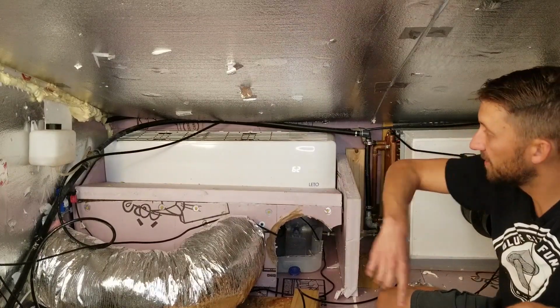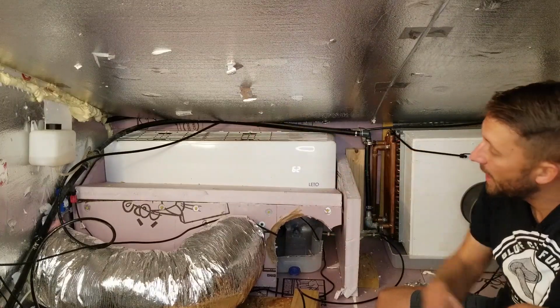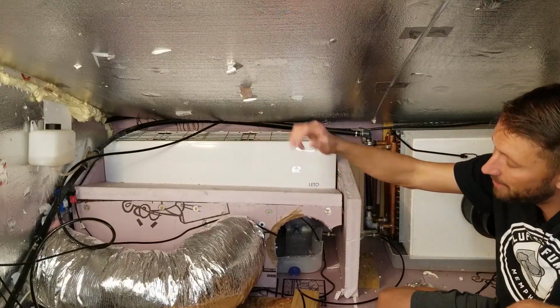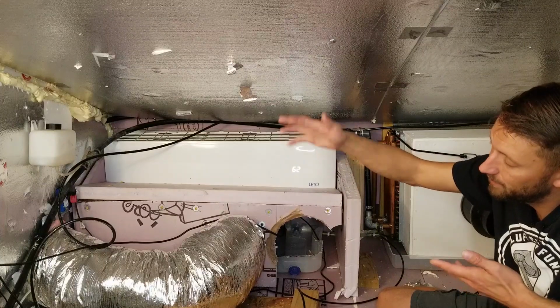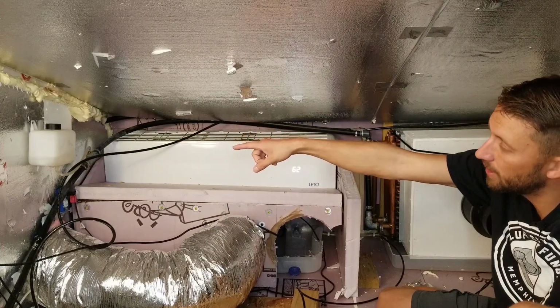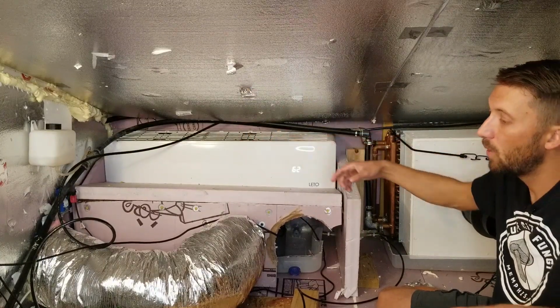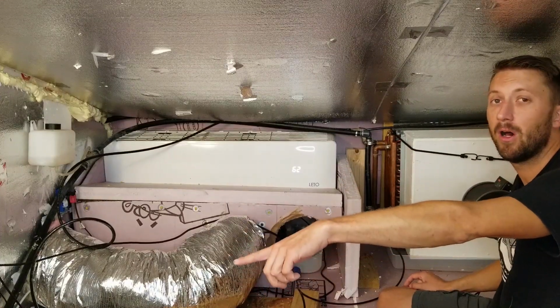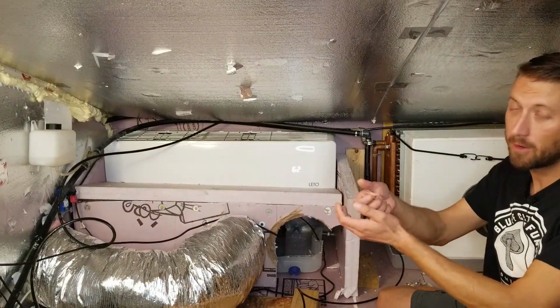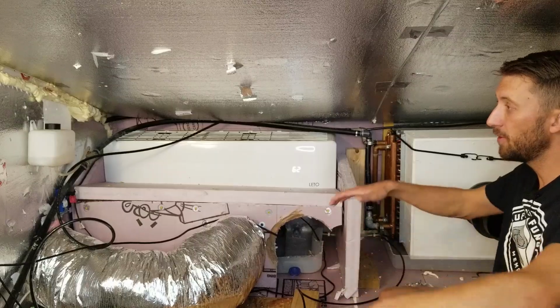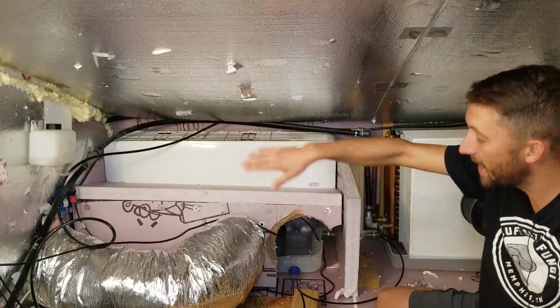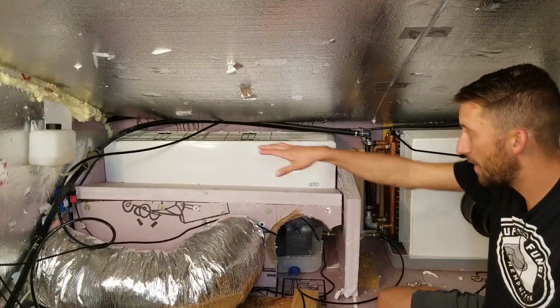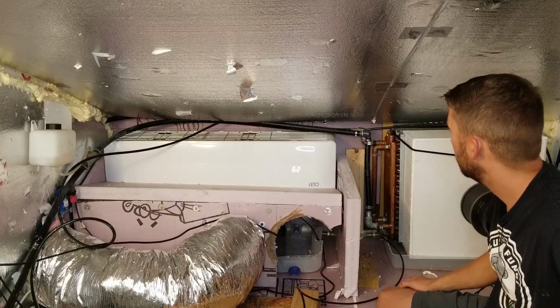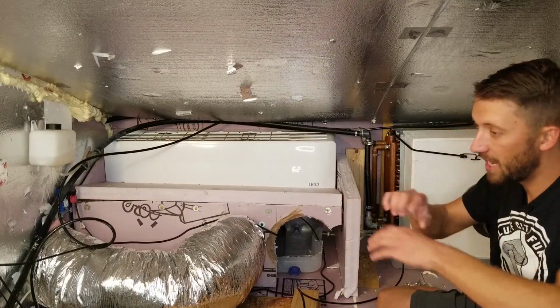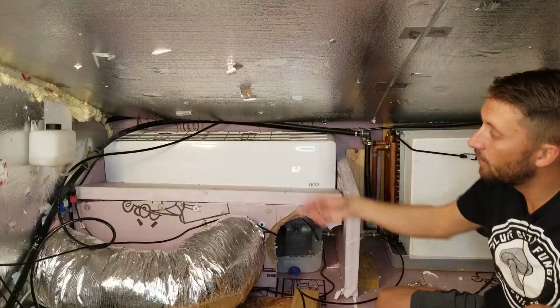With the HRV system, one thing I want to point out is you've got to have a spot for the air to go. I have an expansion tank over there, and I fill the system up from down below. I have a spot to hook my hose up to, and it fills the whole system up and all the air gets pushed out - that has to be at the high spot. So I have that over here with the T. There's different ways to do that - you could just have a big T, but I have a little auto reservoir.